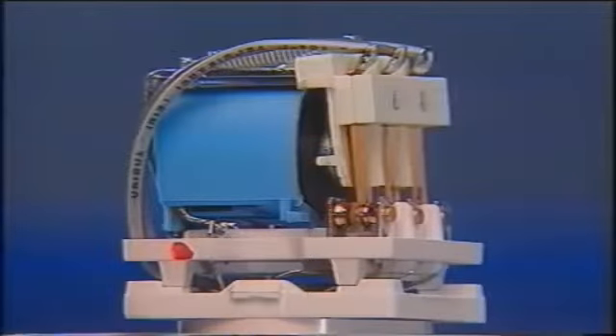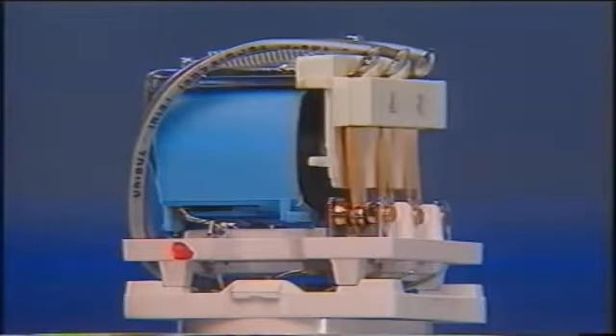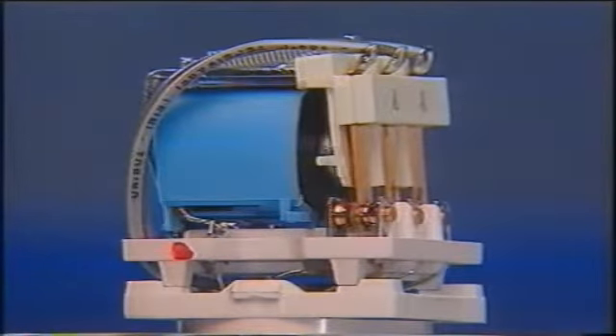Electromechanical signal processing is primarily undertaken by relays or contactors. The relay consists of the coil, the magnet core, and the armature with the contacts. When a current flows through the coil, a magnetic field is produced and the armature picks up. The relay switches. A contactor works according to the same principle, but it is designed to switch power circuits.